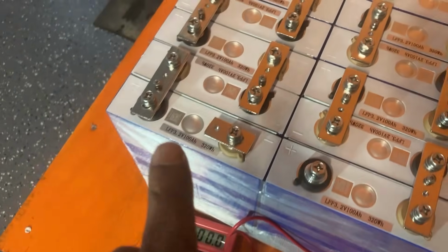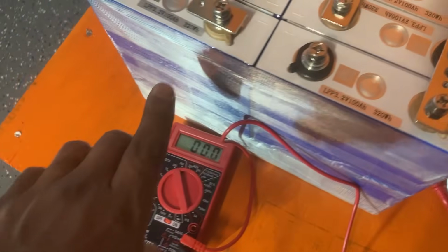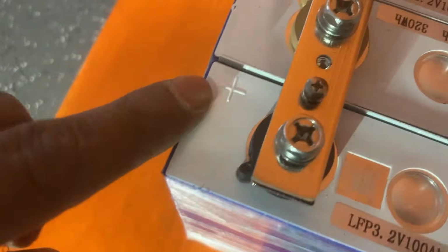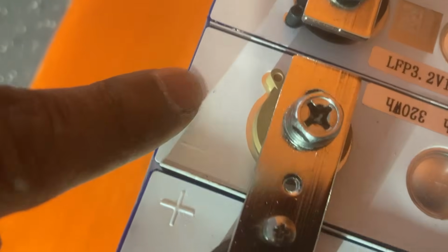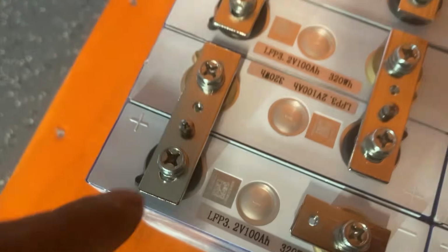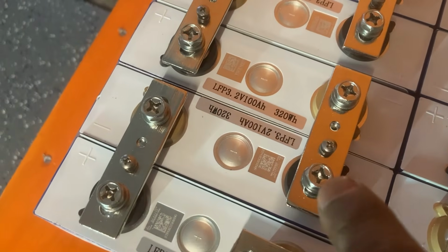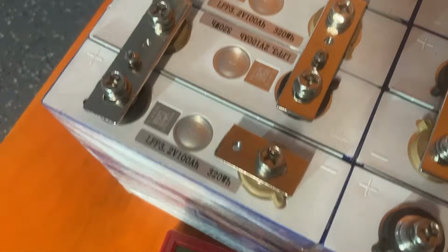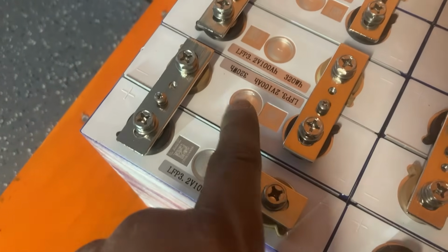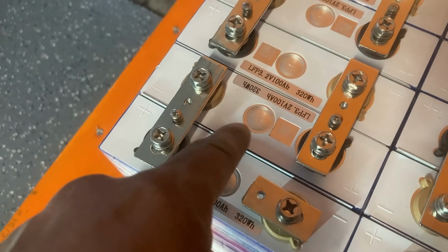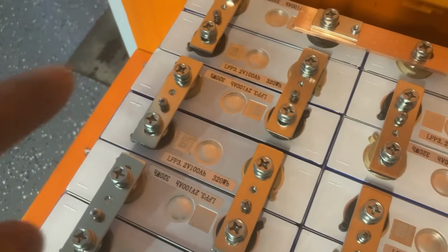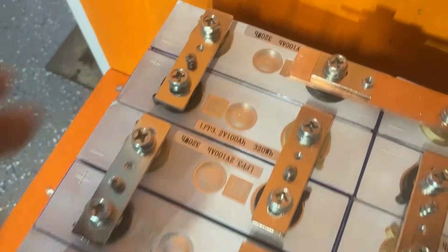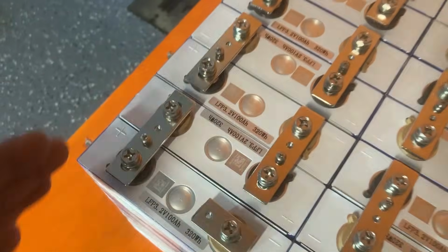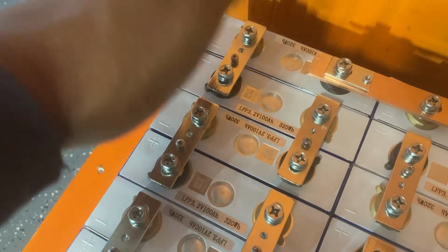One of the things you can see on the battery is that it's in series, so the positive here is connected with the bus bar to the negative of the next battery - positive, negative, positive, negative, positive, negative. So this takes this 3.2 volts and adds it to this one, making 6.4 volts, 9.6 volts, etc. Across the back here, this whole left side is going to be around 24 volts when you get down to it.